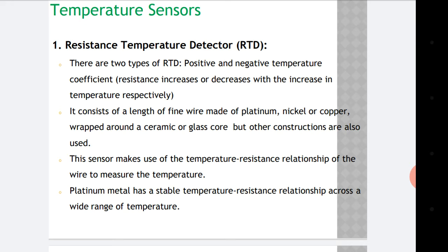That means if there is an increase in temperature, it will lead to an increase in resistance, and if temperature decreases, resistance also decreases. The RTD consists of a length of fine wire made of platinum, nickel, or copper which is wrapped around a ceramic or glass core, though other constructions are also used. This sensor makes use of the temperature-resistance relationship of the wire to measure temperature.